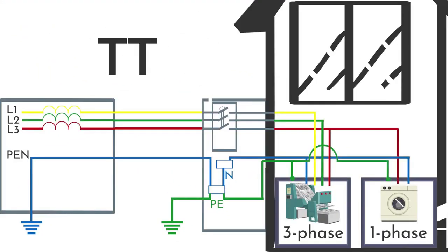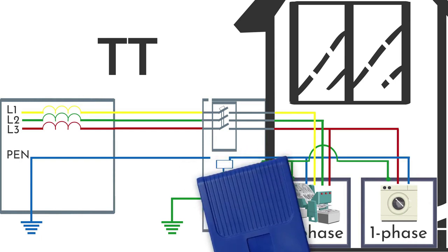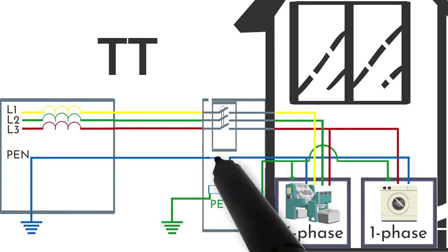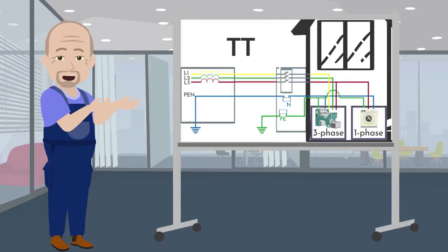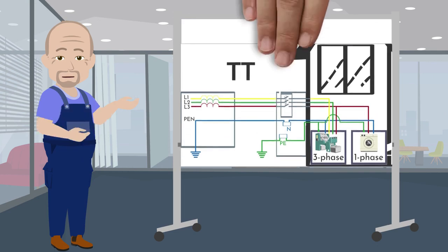Next, let's discuss the TT grounding system. It is used if it is not possible to protect the PEN conductor within the TN-C-S system. This circuit can be described in the following way. The neutral conductor is solidly grounded at the substation power supply source, while the power cable inside the house has 4 cores, 3-phase conductors and a functional zero conductor. The exposed conductive parts of the appliances are grounded by a pin-type ground terminal. For this system, you must carry out thunderstorm protection measures and install an RCD.